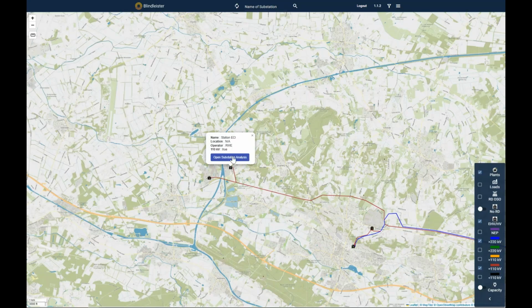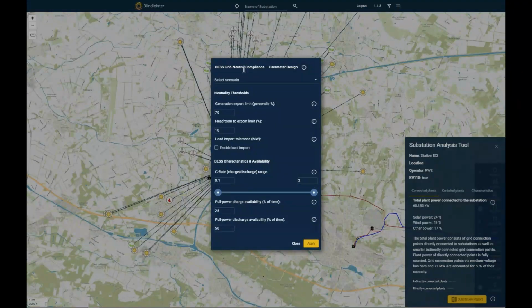So what we do now is a substation analysis based on our grid neutral compliance, which means we try to find a battery that perfectly fits into the generation envelope at this substation. We design a battery size and energy that is not increasing the load sink and is also not exceeding the exported energy, which is important because otherwise we might risk exceeding the power on the line, and then it's very unlikely to get a grid connection allowance from the system operator.